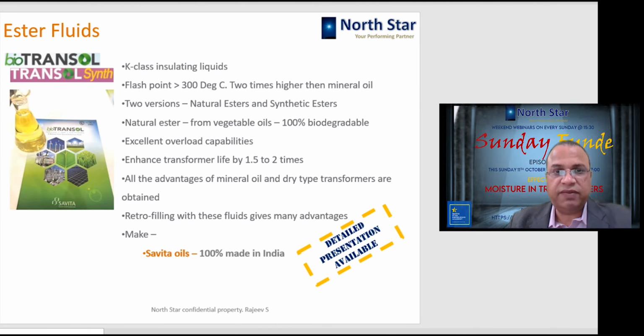As we said, flash point is 300 degrees centigrade and higher, which is 2 times higher than the mineral oil. As I said, two versions are available. Natural ester is made of soybean oil seeds. It is 100% biodegradable, and it has got excellent overload capabilities. The transformer life actually can be enhanced by 1.5 to 2 times.